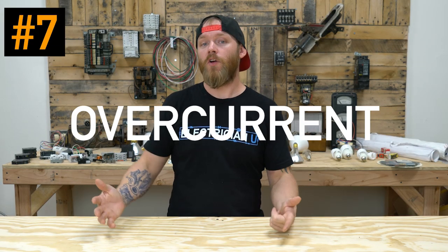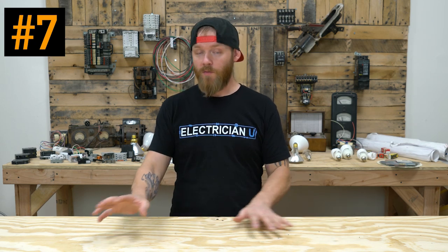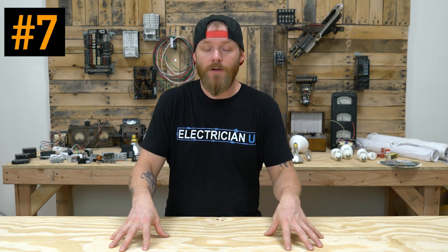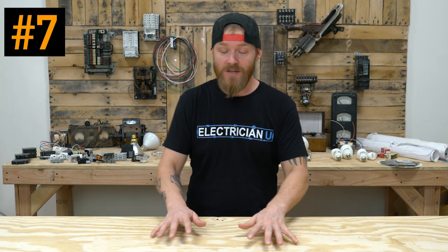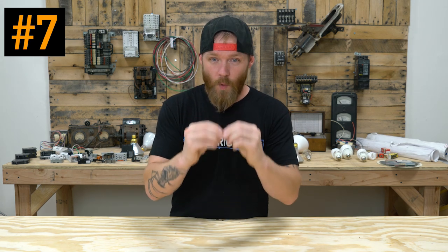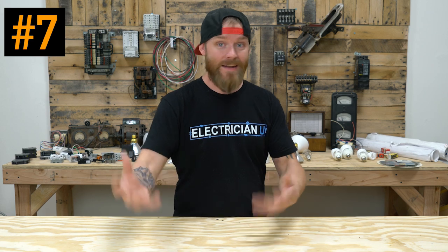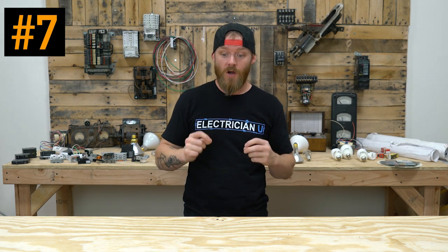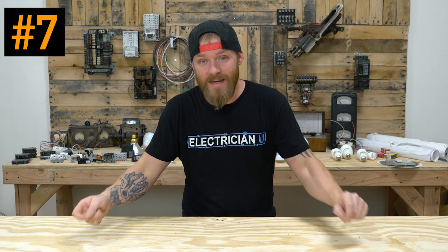Number 7, overcurrent. So a lot of people confuse overload and overcurrent. They kind of are similar, and they're usually referring to the same situation happening. Overload means that the piece of equipment is overloaded. It's the event that's happening to cause that piece of equipment to run in excess of its rating. But overcurrent is talking about what's actually going on inside the wires, the electrical portion of that. So it's any current that's in excess of the rating of that equipment. The overload is basically running the equipment, utilizing it in excess of its rating. But overcurrent is talking about the amount of current going through the wires at that same time for that kind of event.